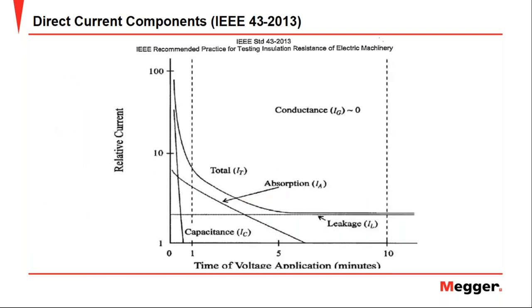Here, you can see the figure shown in the IEEE 43 standard, and it shows us the behavior over time of the four currents. This occurs each time a motor is supplied with a DC voltage. Each time that we supply a motor with a DC voltage, this is the behavior that we can see in the insulation.